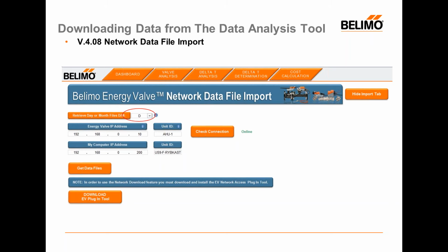What you'll do is you'll select whether you want to retrieve daily or monthly files. You'll have to put in the IP address of the energy valve. So here we see the 192.168.0.10 default address. You can check connection. Essentially, this is like pinging it through command prompt. So it'll make sure that you are communicating with the energy valve.